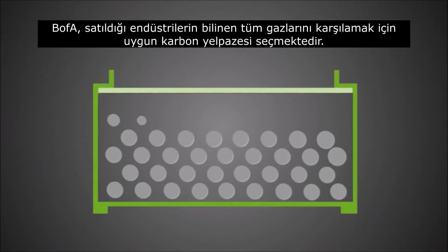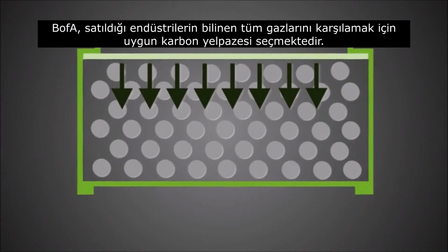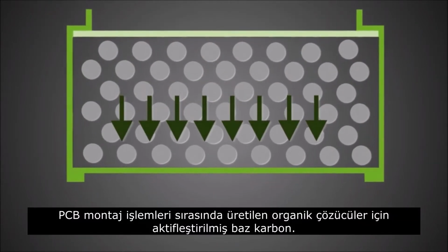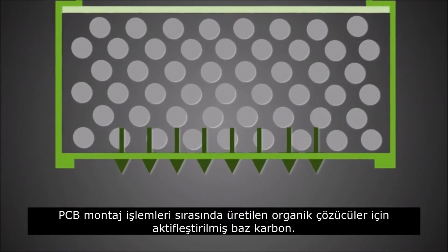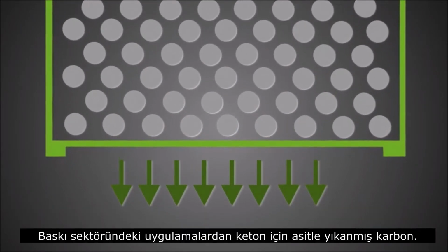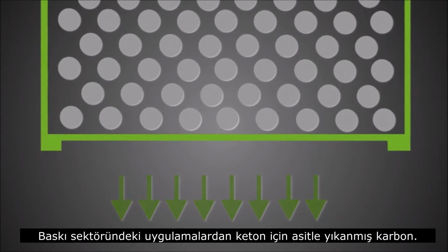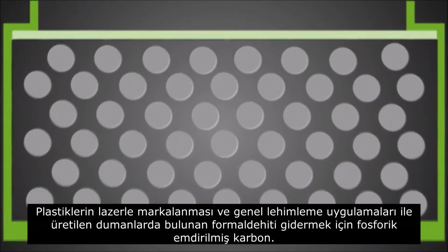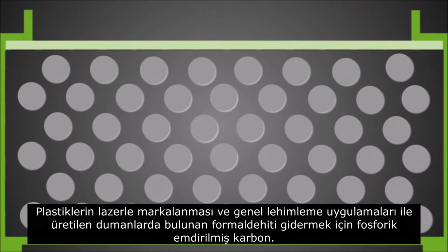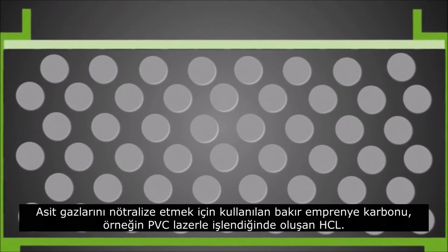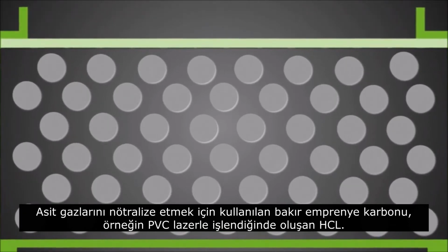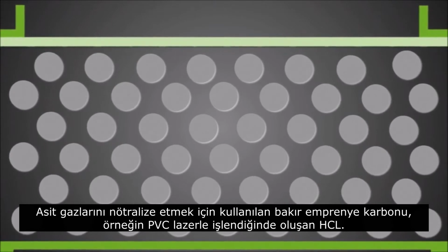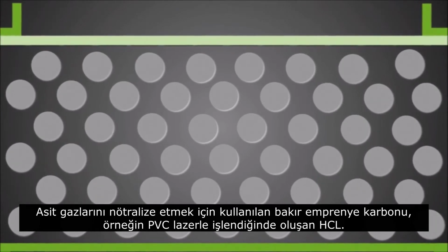Bofa have selected a range of carbons to cater for all known gases of the industries they sell into. Activated-based carbon for organic solvents generated during PCB assembly processes. Acid-washed carbons for ketone from applications within the printing sector. Phosphoric impregnated carbon to remove formaldehyde found within fumes generated by laser markings of plastics and general soldering applications. Copper impregnated carbon used to neutralize acid gases, for example HCl, which is generated when laser processing PVC. Other impregnated carbons are used for applications where specific compounds are generated.